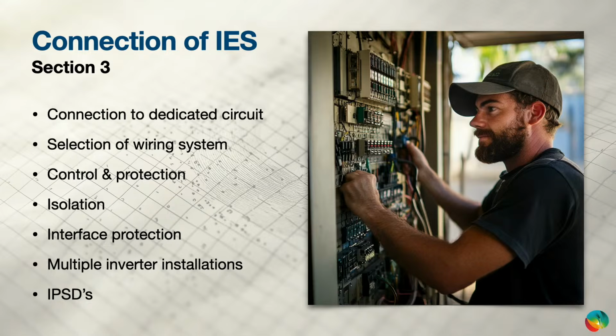Now, I know in New Zealand that this is still a bit of a moving target, whether DNSPs, or lines companies, I should say, actually require it. Certainly in Auckland, in the Vector area, I know it's well enforced. Once you go over a certain capacity, they'll want a dedicated interface and protection device. I've even heard people say in other jurisdictions it's a don't ask, don't tell arrangement, which seems like you're dodging a bullet, but until they start enforcing it. But the standard does give a much higher start point now for interface protection. What used to be 30 kVA in the old 4777 is now raised to 200 kVA. And that's to acknowledge the fact that inverters are capable of export limiting very effectively, and therefore adding extra equipment to kind of limit export as a special device is not necessary to get to above 200 kVA.